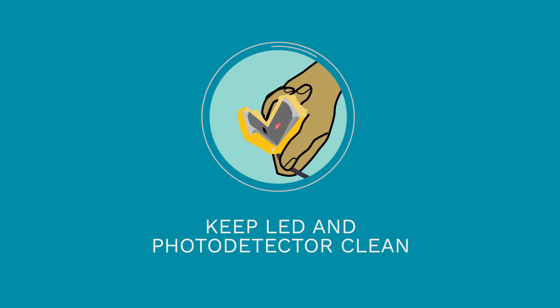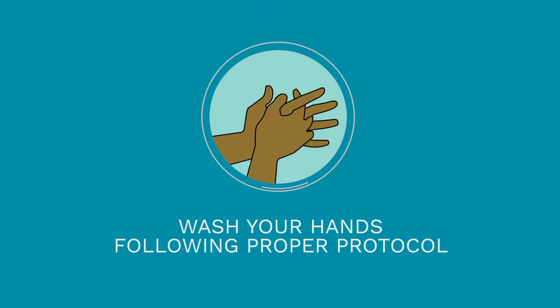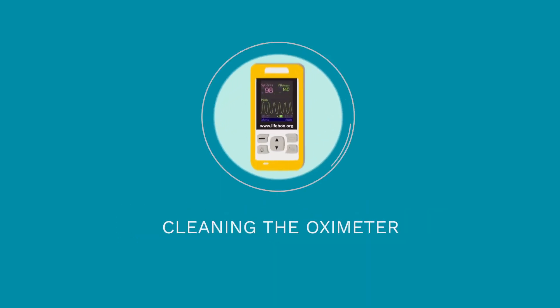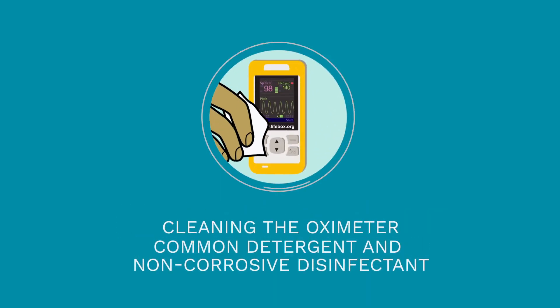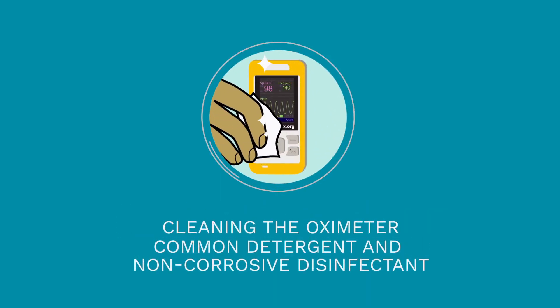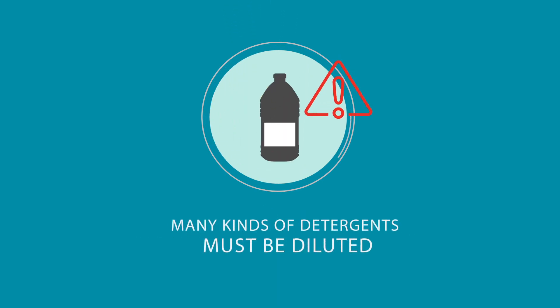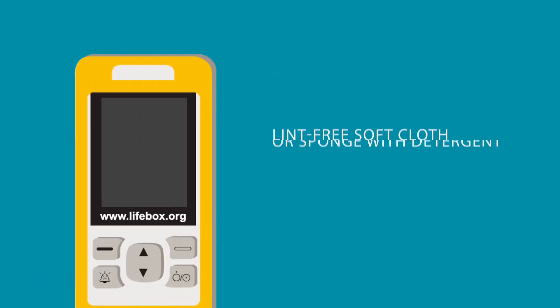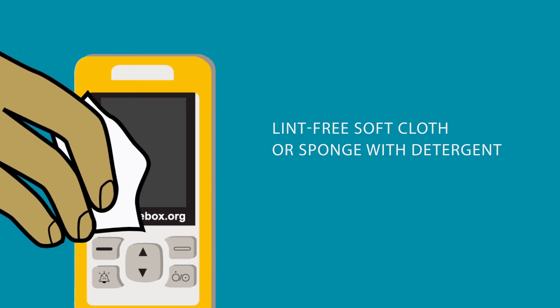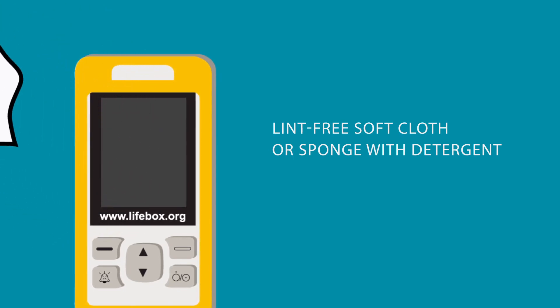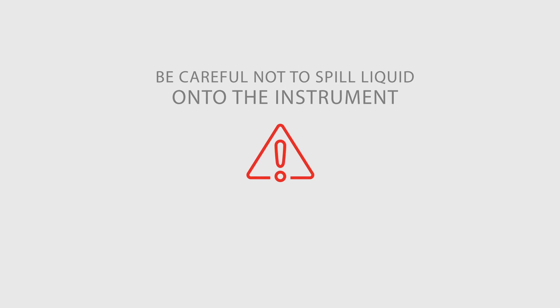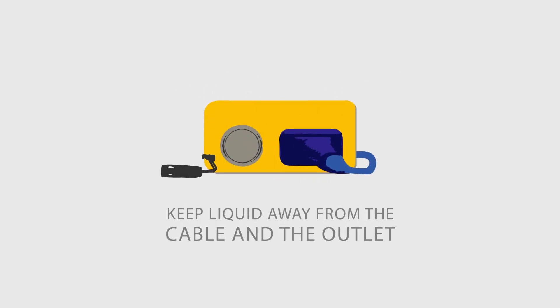Please also remember to wash your hands following proper protocol between patients. The oximeter should be wiped down regularly using common detergent and non-corrosive disinfectant, such as those used in hospitals. Be aware that many kinds of detergents must be diluted prior to use. The oximeter case and screen can be wiped with a lint-free soft cloth or a sponge moistened in detergent. While cleaning the oximeter, be careful not to spill liquid onto the instrument and do not allow any liquid to spill inside the oximeter. When wiping the side panel of the oximeter, be especially careful to keep liquid away from the cable and the outlet.